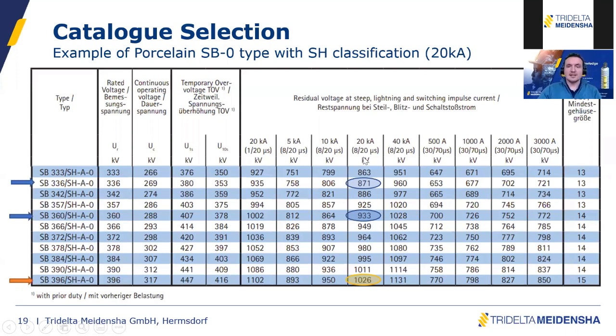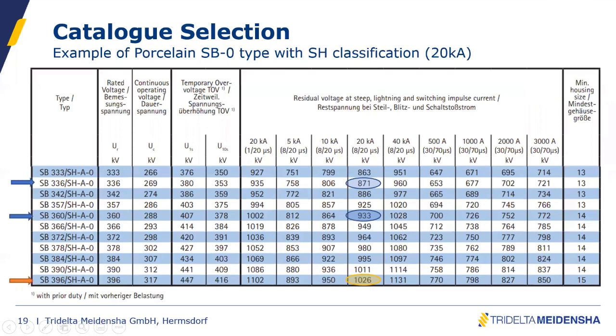So you can see here for each selection the different protection level which is associated, because this is the next step. Once you have defined your rated voltage, you have to look at the associated protection level or residual voltage to make sure it fits your system.